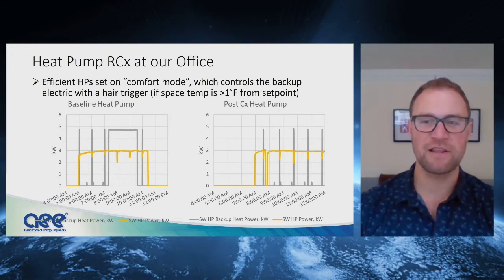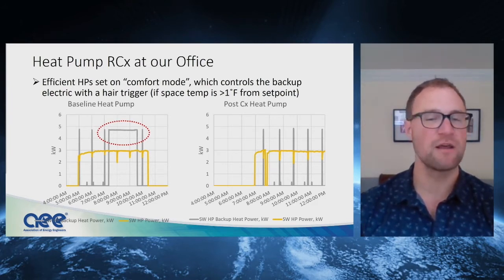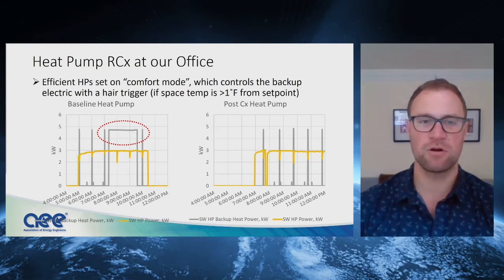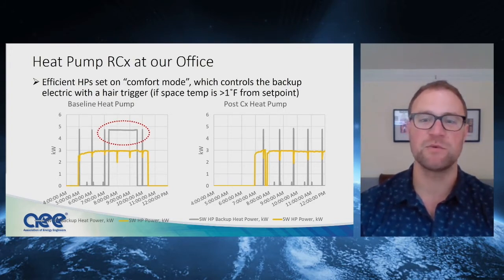There are two figures here. The figure on the left shows the baseline, as observed, and the one on the right is after we commissioned it, or retro-commissioned it in this case. The gray line is the backup heat power, and the yellow is the compressor and fan power, the heat pump side of things. As you can see in the dotted red line there, in the morning when the occupied hours begin, the backup heat comes on right away and stays on because it's trying to maintain 1 degree of set point as quickly as possible, which is just not realistic or necessary really. So just by relaxing that requirement, we eliminated most of the backup heat from coming on, as you can see on the right, and now the heat pump is doing the work that it was supposed to do.